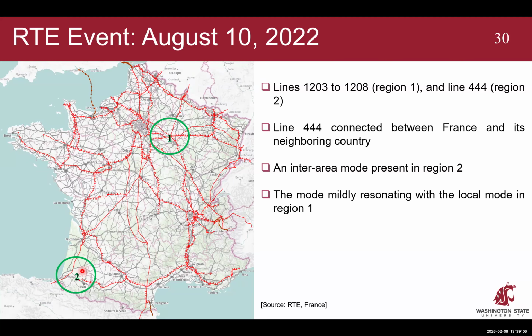This is because during this event, there was a forced oscillation that excited the inter-area mode between France and Spain, which is why the transmission line connecting France and Spain showed significant oscillations. It wasn't a strong resonance event, it was weak resonance, but this analysis was still able to provide insight that this was a resonant event and not just a local one.